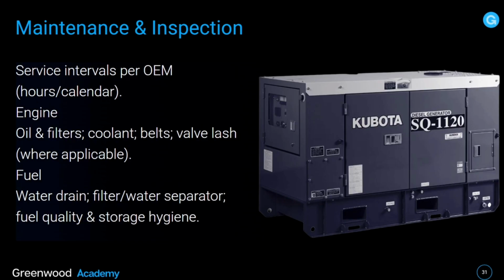There's fuel, there's oil, there's air, there's all these filters that need to be checked, and you need to document your maintenance schedule. So you're looking at service intervals per OEM, hours per calendar, engine, oil and filter, coolant, belts, valve lash where applicable, fuel, water drain, filter, water separator, fuel quality, and storage hygiene.